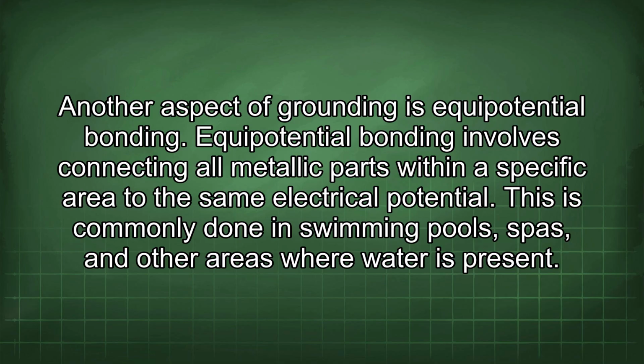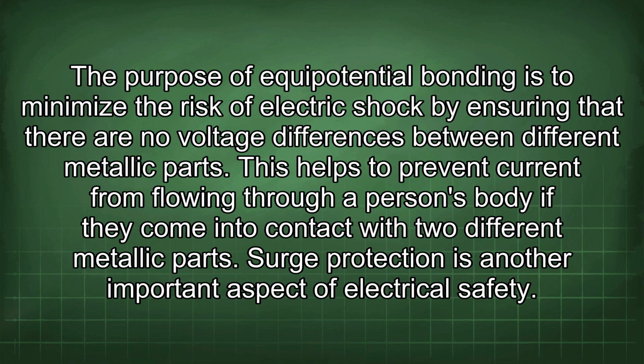Another aspect of grounding is equipotential bonding. Equipotential bonding involves connecting all metallic parts within a specific area to the same electrical potential. This is commonly done in swimming pools, spas, and other areas where water is present. The purpose of equipotential bonding is to minimize the risk of electric shock by ensuring that there are no voltage differences between different metallic parts.